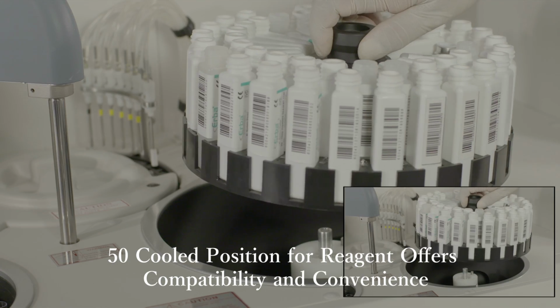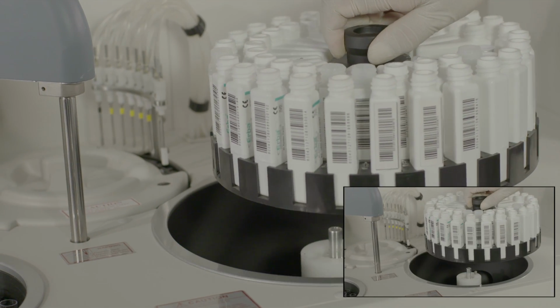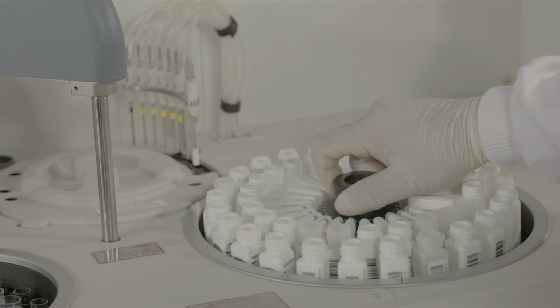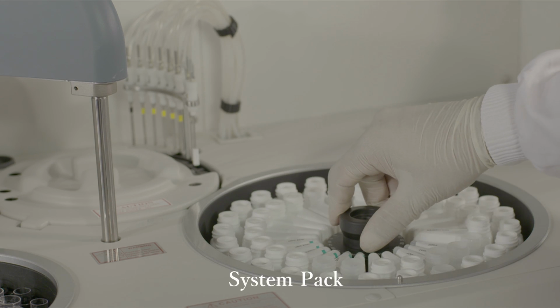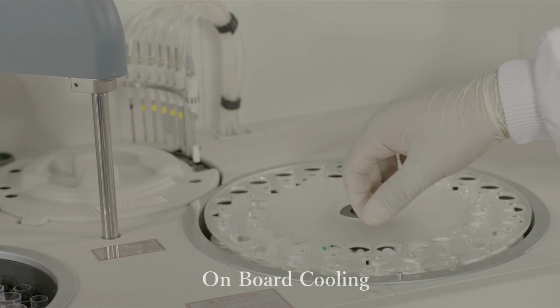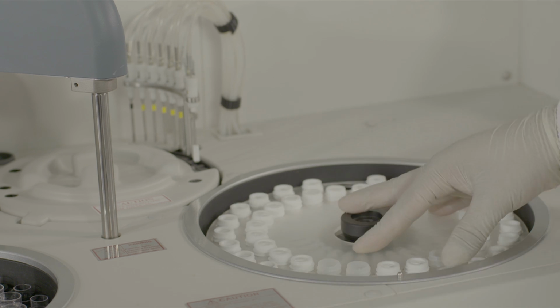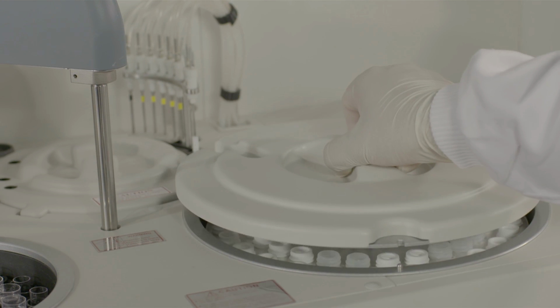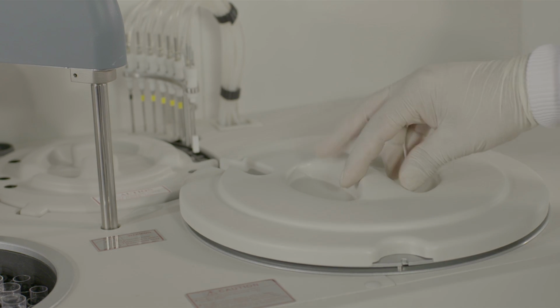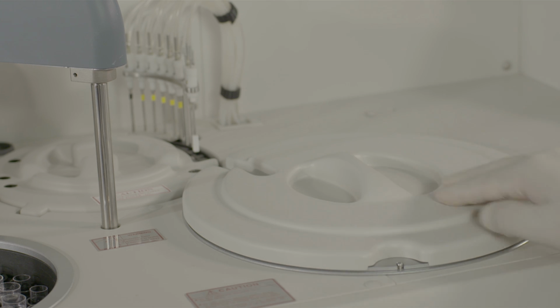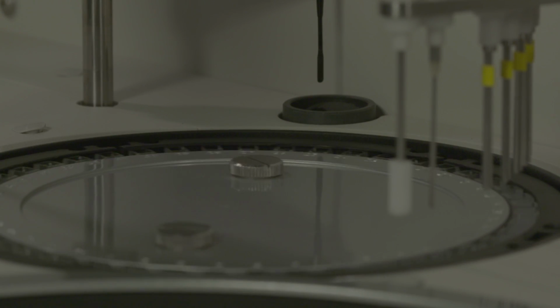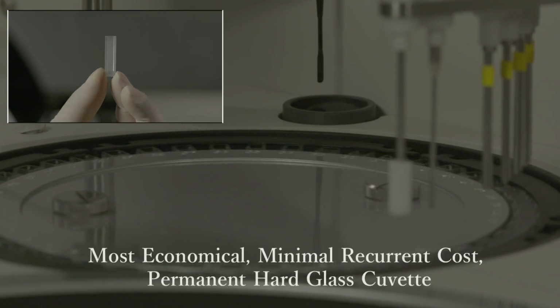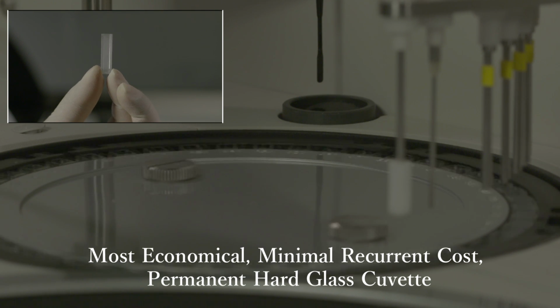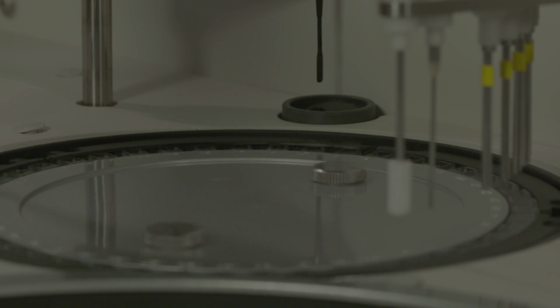Reagent carousel consists of 50 onboard positions for placing dedicated system pack reagents. Onboard cooling ensures longer shelf life and better stability of reagents and consistently accurate results. Reaction cuvettes are made of permanent hard glass, ensuring long life and cost effectiveness.